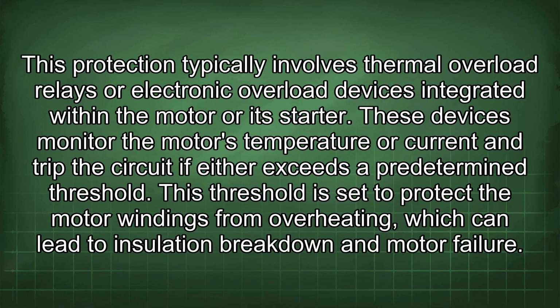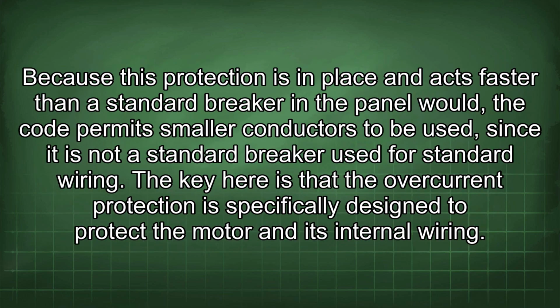This protection typically involves thermal overload relays or electronic overload devices integrated within the motor or its starter. These devices monitor the motor's temperature or current and trip the circuit if either exceeds a predetermined threshold. This threshold is set to protect the motor windings from overheating, which can lead to insulation breakdown and motor failure. Because this protection is in place and acts faster than a standard breaker in the panel would, the code permits smaller conductors to be used, since it is not a standard breaker used for standard wiring. The key here is that the overcurrent protection is specifically designed to protect the motor and its internal wiring.